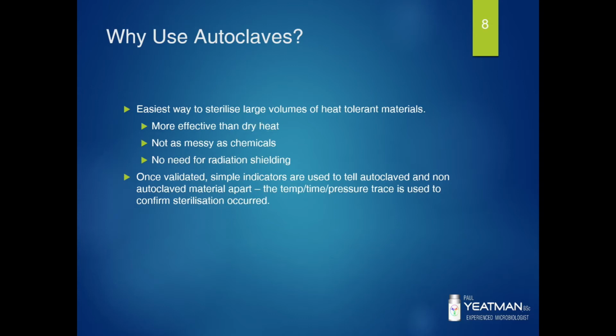Autoclaving is better than chemicals, as in chemicals that are toxic, because water is a chemical. You would need large volumes of chemicals, and they would likely contaminate what you were sterilising, and you would need to extensively clean up after use. This equals time and money, and that can be expensive. There are also disposal problems, which again cost time and money. And steam evaporates quite quickly, and any residue converts to water or water vapour, which makes clean up pretty much automatic for an autoclave.